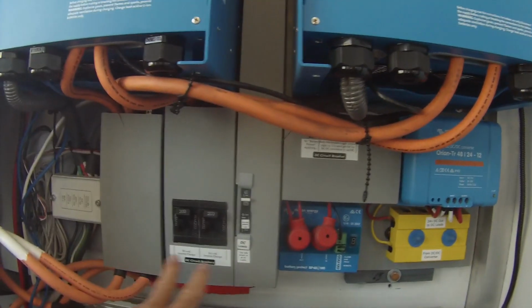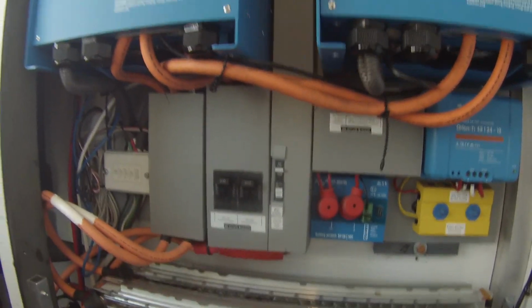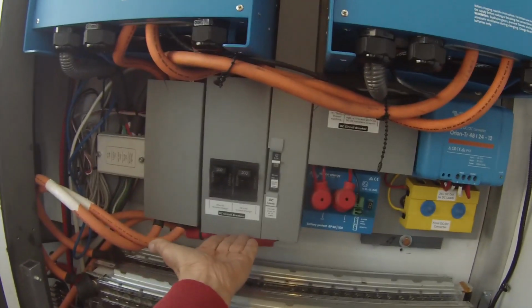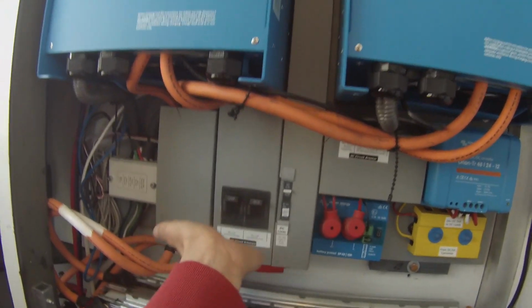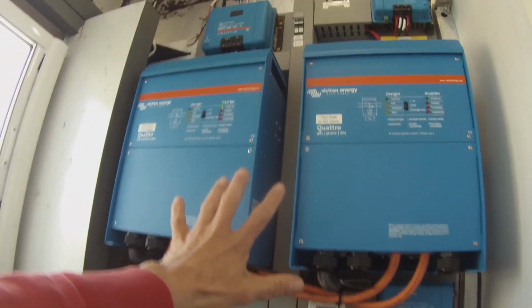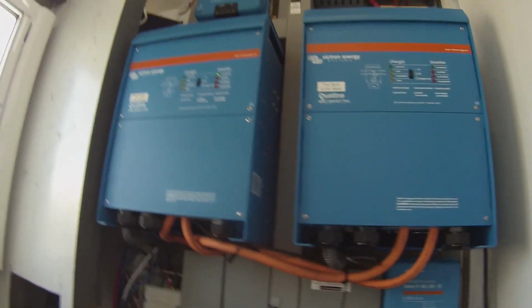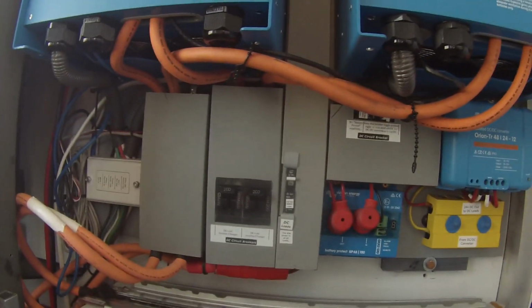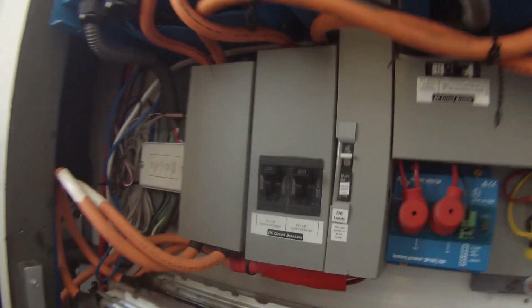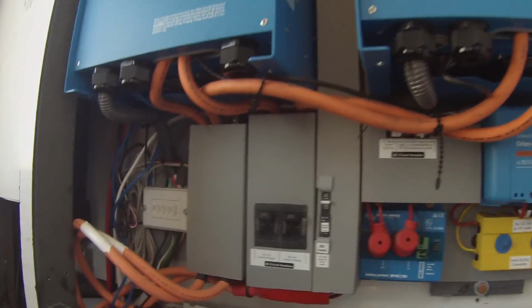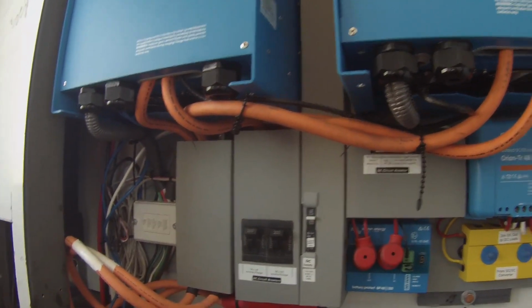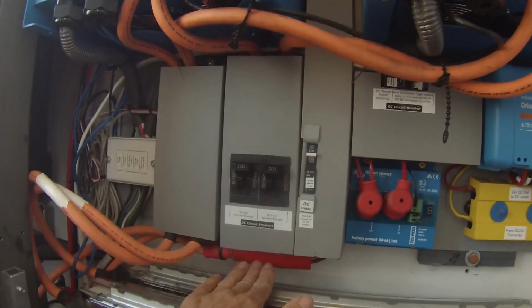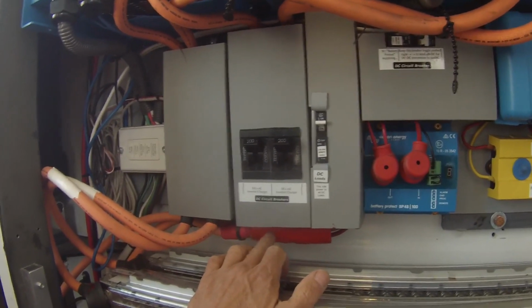You might ask, don't you have a main breaker here? Yes, I do, but that controls it from this point up, so it shuts everything off to the Victrons so I can work on them. But what you don't see is that my DC loads are tied in on the back side of this—you can see those little red wires going down there, tied into the lower side of the breaker. So even though these breakers may be shut off, my DC loads will still be live, with 48 volts coming into the bottom of this.